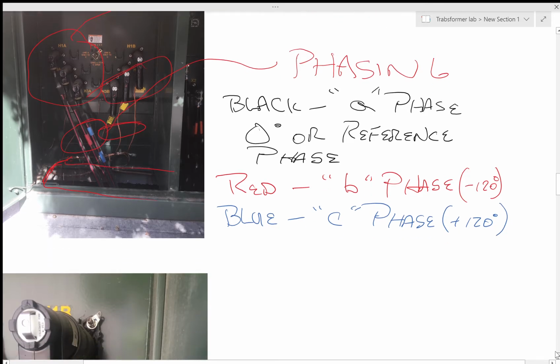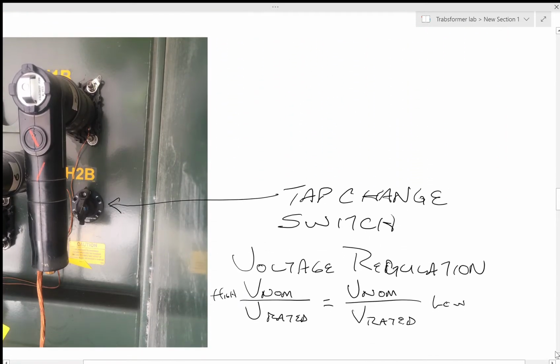So keep on going up. Again, here's the lightning arrestor, all it does is provide a quick path for lightning to go to ground. The most important thing in here is your tap changer. The tap changer is basically so you can regulate the output voltage of your transformer.